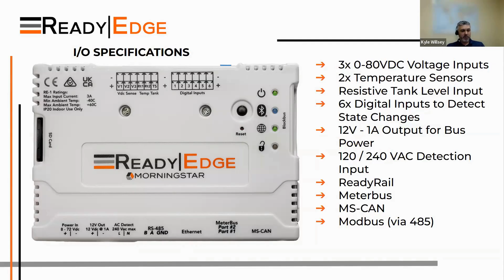It has a really wide power input rating, 8 to 72 volts, so it's suitable for 12, 24, or 48 volt nominal systems, and a really wide temperature range, minus 40 C to 60 C. But it is indoor rated, just like the vast majority of our charge controllers, and needs to be installed in accordance with those provisions for indoor use products, meaning inside of an enclosure.